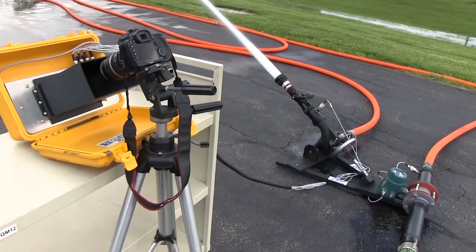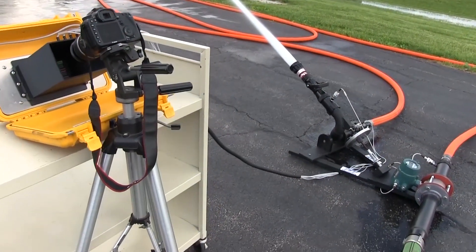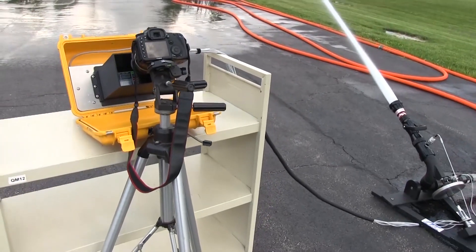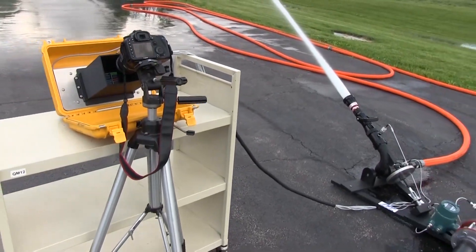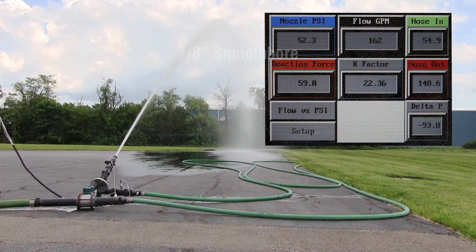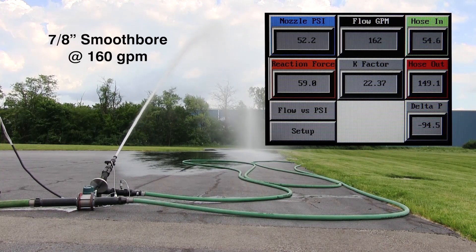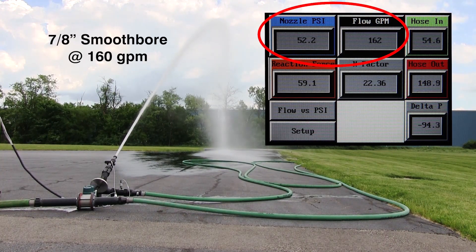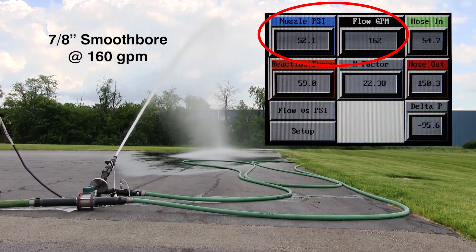Using our flow test device described in our introductory video, we begin by observing flow and pressure data of a 7/8-inch smoothbore flowing at 160 GPM, plus or minus 2 GPM. Our 7/8-inch smoothbore is flowing at about 160 GPM and showing a nozzle pressure of about 50 PSI.